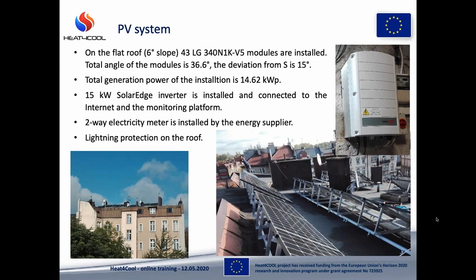The PV system, which was implemented, consists of 43 LG panels, each of power 340 watts, and in total the system gives 14620 watts of power generation. The DC-AC conversion is performed by a 15 kilowatt three-phase SolarEdge inverter, and the installation has around 15 degrees deviation from the south to the west. Also on the roof we installed over 10 lightning protection masts, which secure the PV installation and also the building.